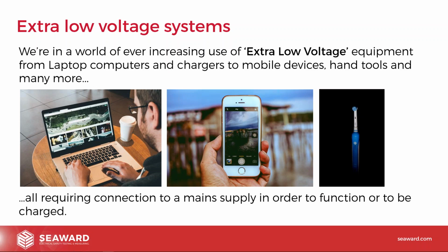So carrying out a visual inspection on these things and making sure that they are working correctly, that the charger's correct, it's the right voltage, it's a genuine charger, and all these sorts of things, is part of the risk process. It may just be a visual inspection, it may be a very quick process, but generally for everything that's on the asset register, we would want a label on to say that it had been tested, even if that's just a visual inspection to make sure that it's there and there's no signs of damage and things like that.